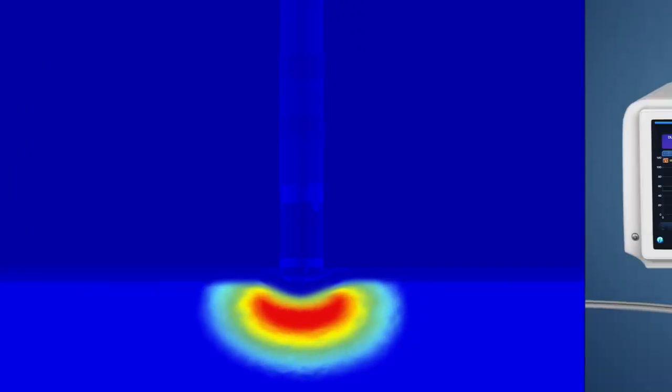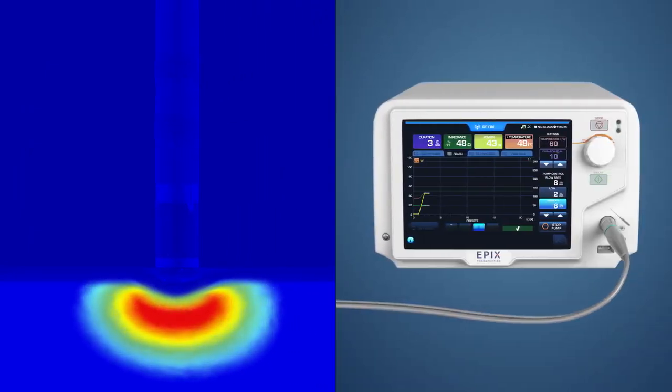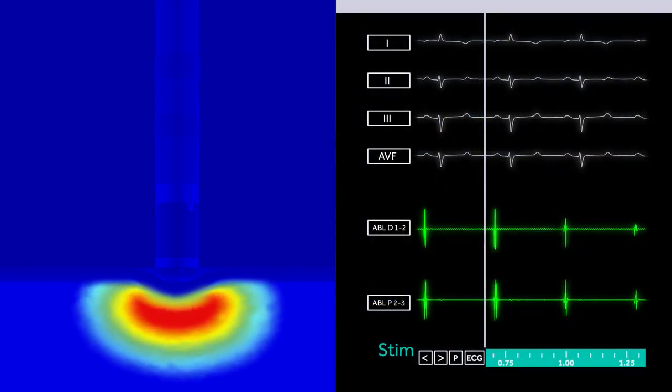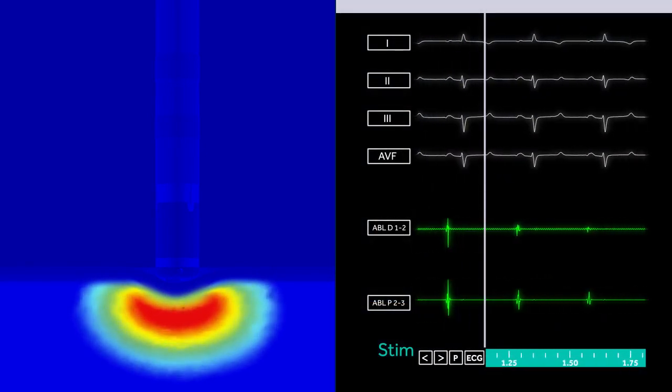Temperature, impedance, and electrogram attenuation are key biophysical parameters which are used to assess lesion formation with the Diamond Temp ablation system.